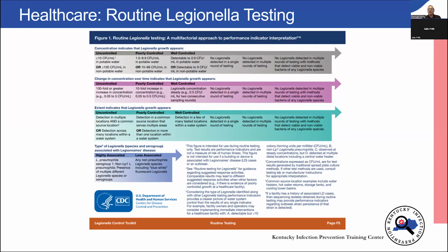They understand that there may be a little bit of positivity for Legionella in cooling towers and other areas. There's also a more difficult mechanism of getting into the water, getting into the droplets, and then getting to people. So that's why they have a higher threshold value for that. But you write that into your water management plan as well: our cooling towers are going to be tested, and if we have anything above 10 CFU, we are going to reevaluate the biocides being applied and ensure that they're being applied properly, and then possibly do a cleaning of the cooling tower and bring our water treatment professional in for that.